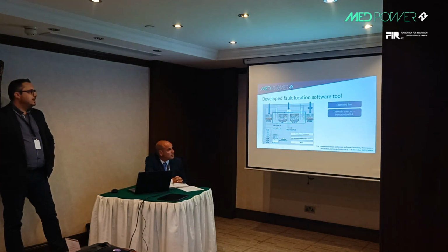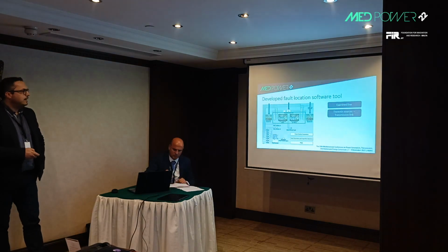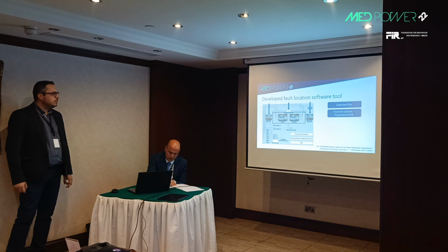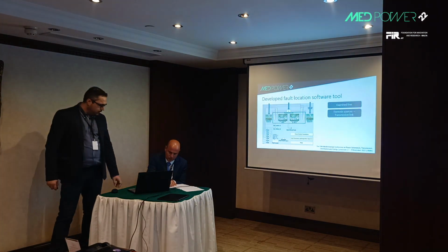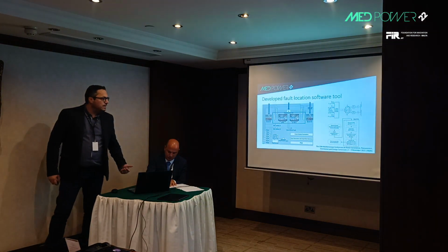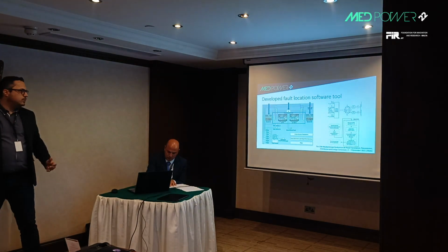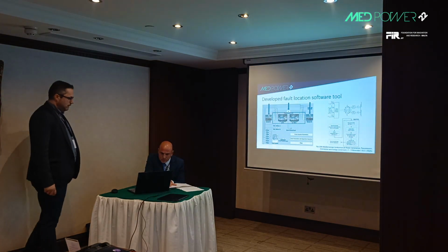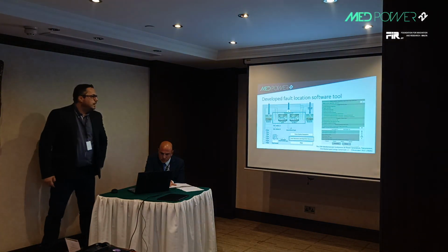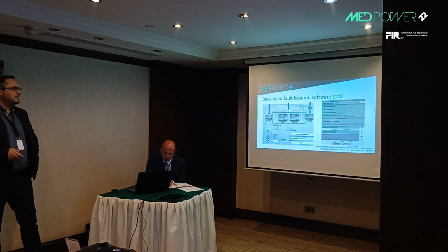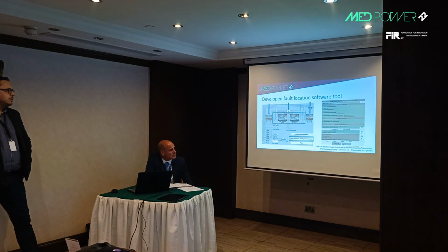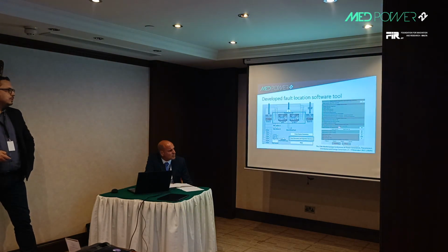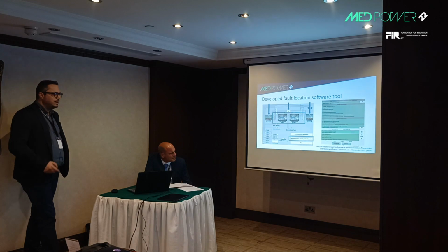The equivalent external sources and the equivalent transmission link connected in parallel to the transmission line under investigation are also calculated with the use of another algorithm which tries to reduce the external grid around the transmission line of interest. The user may choose the desired fault location algorithm. They can choose the desired fault distance, the fault type, the compensation of the line if it exists, the fault inception time, etc.